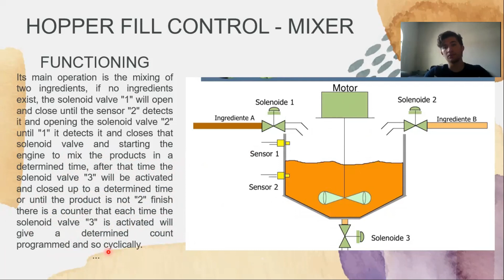Then it opens solenoid valve 2 until sensor 1 detects, closes that solenoid valve and starts the engine to mix the products for a determined time. After that time, solenoid valve 3 will be active and close after a determined time or until the product is finished. There is a counter that each time solenoid valve 3 is active, adds a determined count, programmed, and so cyclically.